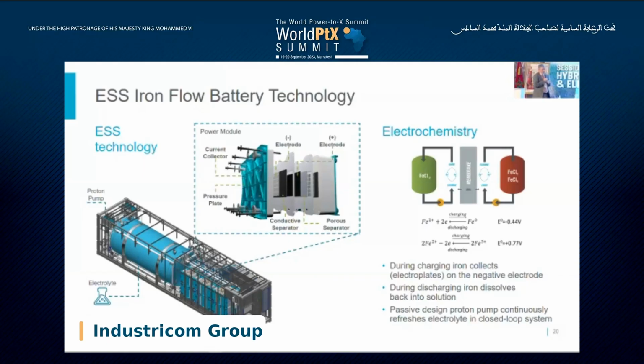In a flow battery, the energy is stored in the electrolyte, or rather two electrolytes, forming the two halves of the battery. The concept got a lot of interest for long duration, bulk storage, because unlike a closed cell system, you have a reactor system with a fixed cost, and the capacity of the battery is determined by how much electrolyte you flow through it. If you want to double the duration, you flow twice the electrolyte through the system. That's the underlying principle. I won't go into too much chemistry, but the interesting thing about the ESS system is that both electrolytes are the same stuff—they're both ferrous chloride, FeCl2.